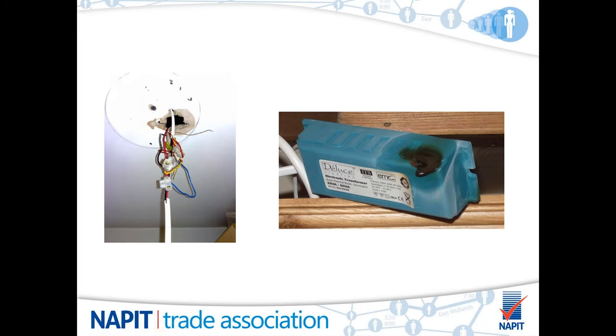Once again, this picture is showing the use of a connector block. Now, in this instance, the connector block has been used behind a light fitting, and as you can see, either through loose connections or the exposed parts, burning has occurred in the lighting transformer, which again, above the ceiling, nobody's going to know until it's possibly too late.